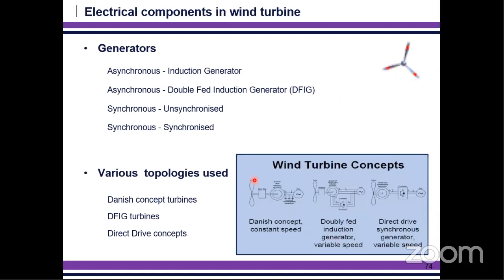Generators of different types: induction generator, doubly fed, synchronized, unsynchronized, synchronous generators. And for topology, when you look at the Indian scenario, they mostly used the Danish type and the DFIG, and now the much more popular direct drive concept. The Danish type is the one they installed long back. Still you can see it in some of the wind farms. For example, at Kayatar you can go and see this kind of wind turbines still.